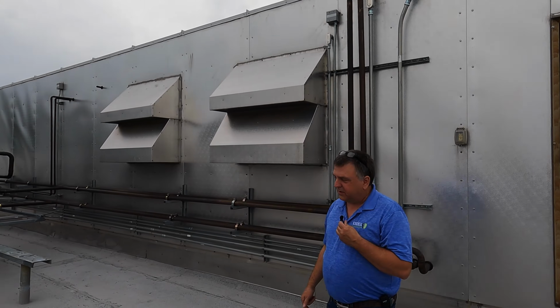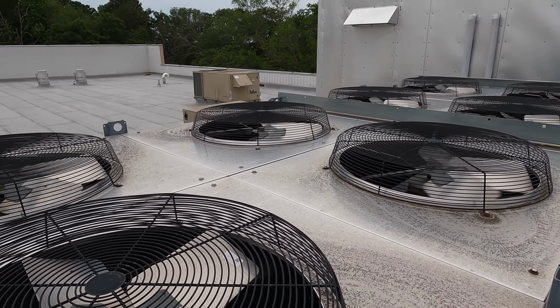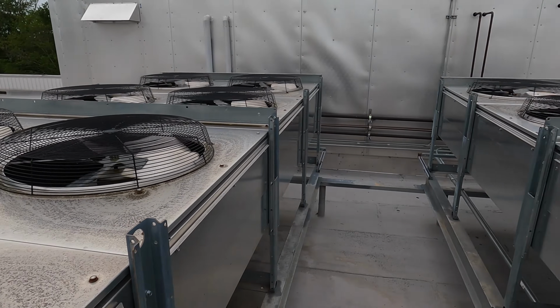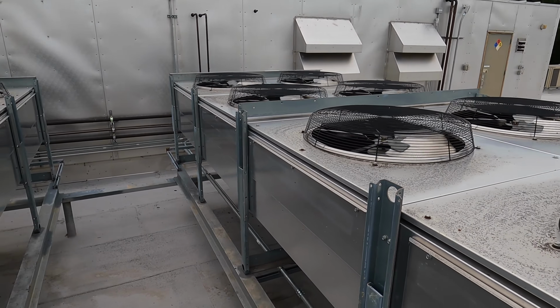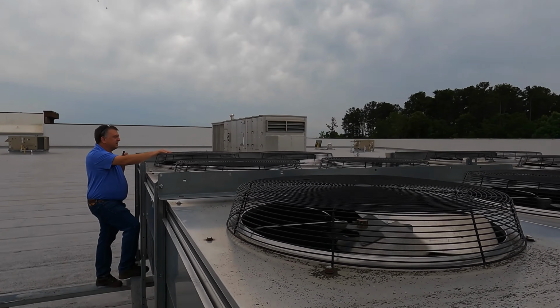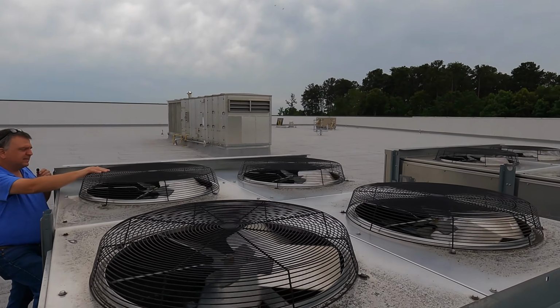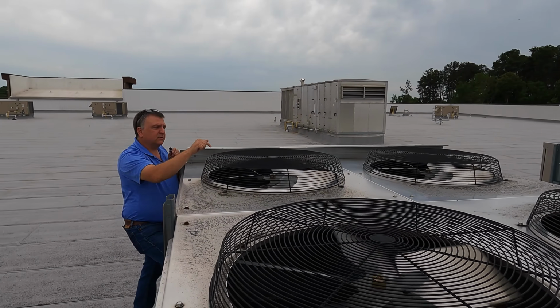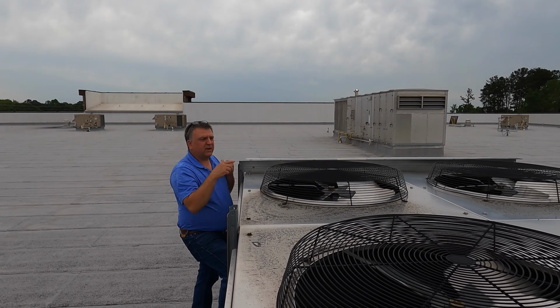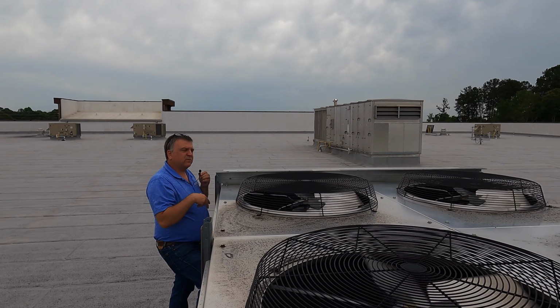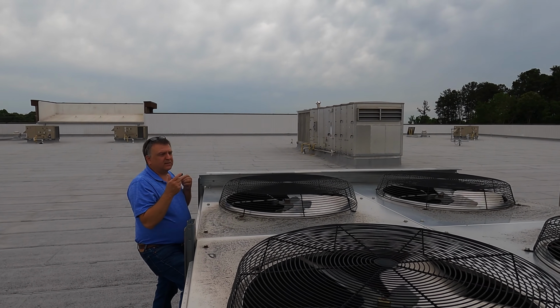There's a lot of heat. You wouldn't think it, but look at there, there's 2 stacks of condensers feeding that one rack. That's a lot of gas. That's a lot of heat. We're sending a 0 to 10 volt DC signal to these motors, and they're coming on as needed. The higher the voltage, the faster it runs.